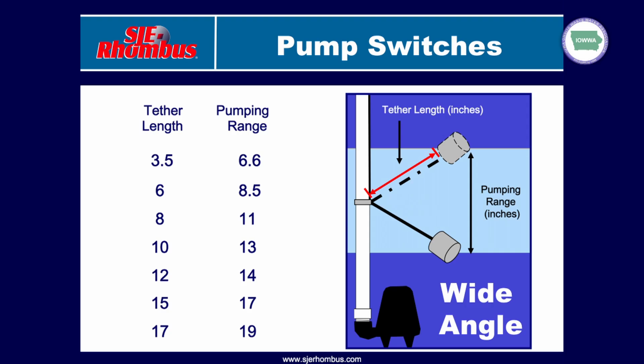All right, on a pump switch, we're going to control the length of operation for the pump by the length of tether that we come out from our discharge pipe or from our float tree. As you can see on the chart, the longer the tether, the greater the pumping operation range from off to on. All right, and you hit a certain limitation, you get enough cable out there and there's going to be no benefit to going additional cable. Typically that's going to be about 20 inches so far as the tether goes. You can run out another 20 inches beyond that and you're not going to get any additional pumping range.